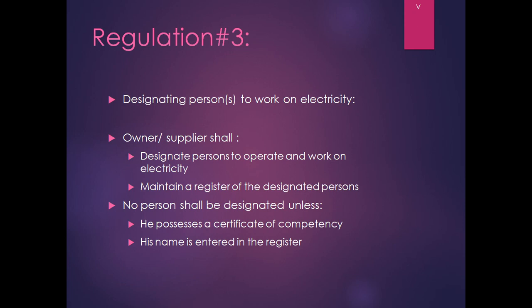So first, the owner or supplier or the contractor has to designate some person for working in the electrical systems. Secondly, he has to maintain a register which he may have to produce in front of the electrical inspector. Many a time the electrical inspector actually asks for the register. So there shall be a register where the persons who are designated for electrical works, their names shall be present. Also, for designating a person, you must be confident or you should have some proof that he possesses a certificate of competency. So these are the three requirements for designating a person to the electrical works.